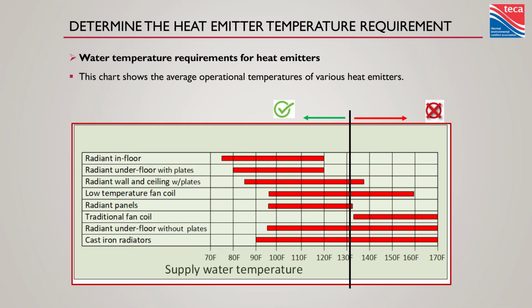You've got your radiant in-floor working in the 75 to 120 range typically, not much more than that, or I've seen some very expensive marble floors cracked by too hot of water. But even at 75 degrees, barely above room temperature, we can heat a space with radiant floor heating. Radiant underfloor, it's going to start a little higher, but still going to max out somewhere around 120.